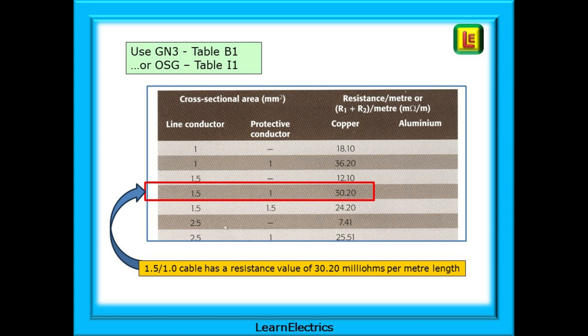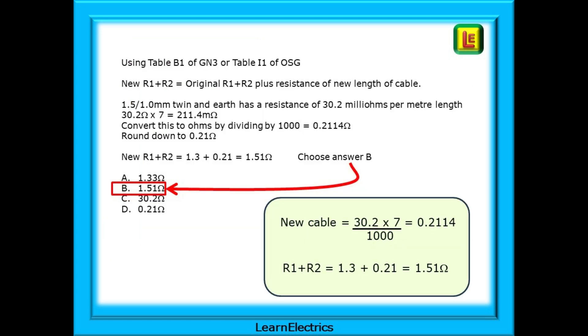Find 1.5 by 1 mm cable, as shown here. It tells us that this size cable has a resistance value of 30.2 milliohms per meter length. Now we can use that resistance value in a simple calculation to find the resistance of the new 7 meter cable, and then the total resistance of the whole circuit.